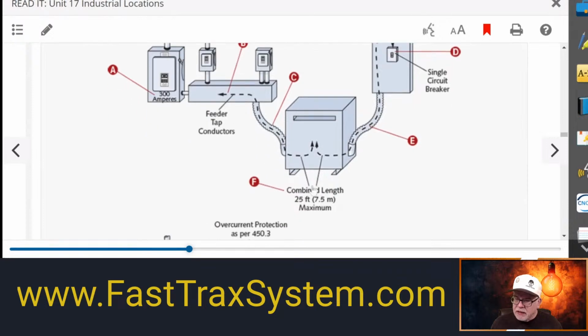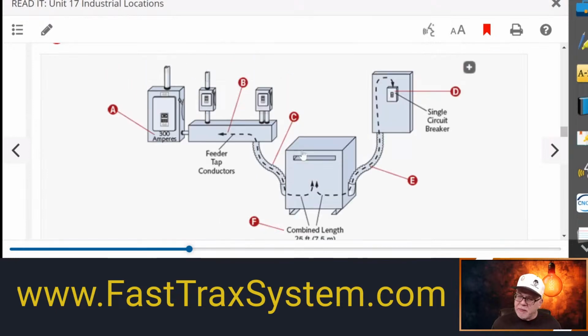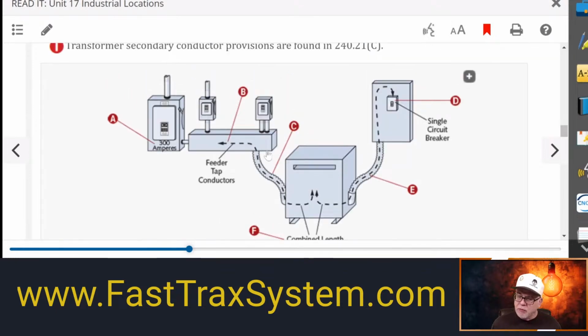All right. Now, that rule, we said you have a maximum of 25 feet combined. So the length of this tap right here, plus the length of the secondary, combined cannot be more than what? 25 feet. Now, why do we do that? That's because typically in doing this, the transformer is in close proximity to the panel that it supplies. Right? And so there are caveats to do this.